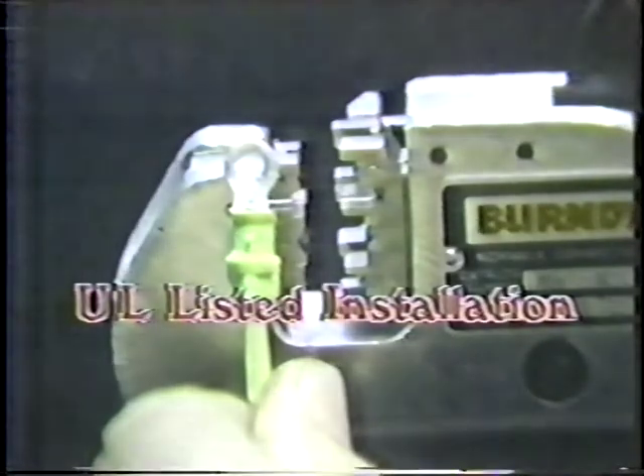To install, place the terminal stop in the up position for a terminal. Insert the terminal and squeeze the handles until the first click is heard. Once started, the handles won't release until the crimp is completed. Now insert the conductor and finish the crimp. When completed, the tool will release, enabling you to remove the terminal.